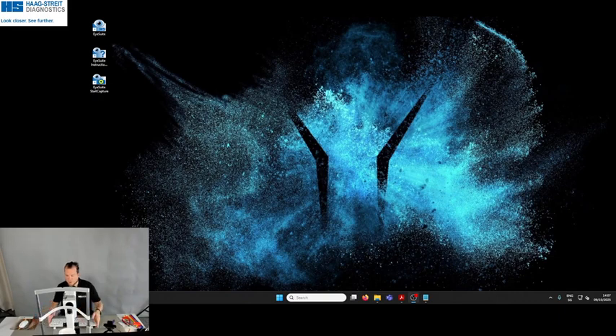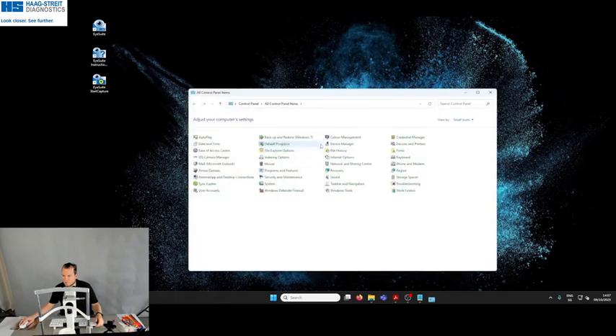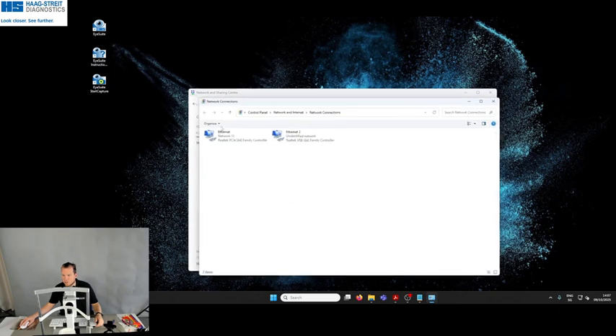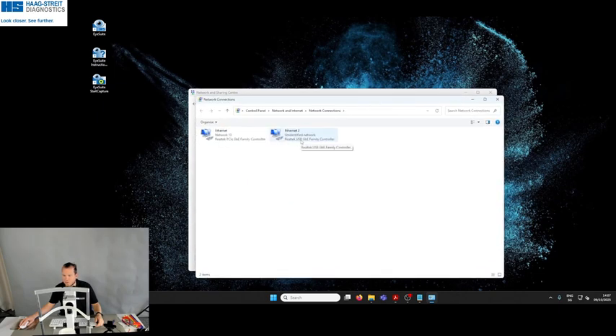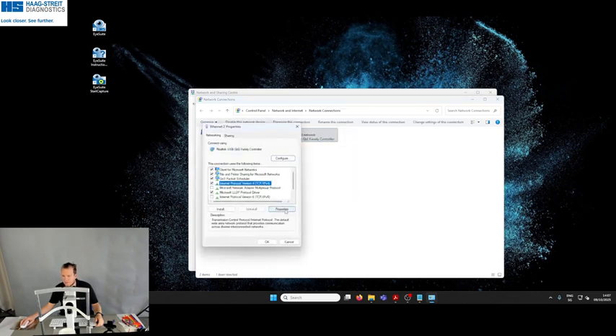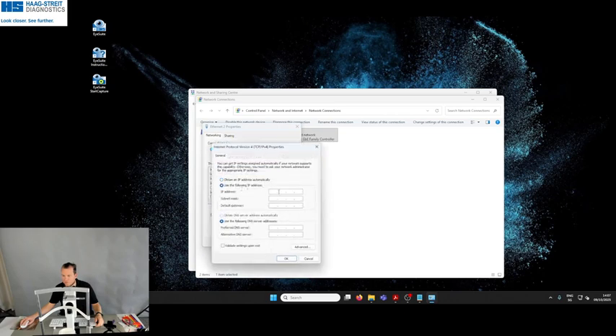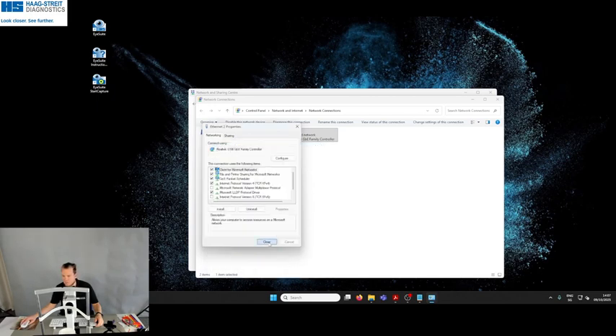To connect to the Elara, connect it to your PC and bring your PC into the default IP range. For this, we go to the control panel, network and sharing center, change adapter settings, and we have here the USB to Ethernet adapter that I use for this setup. Go to Properties, IPv4, Properties, use the following IP. The default IP is 172.16.42.23. So we bring this PC into the same range with 20. Subnet mask, we can take the default and click OK.